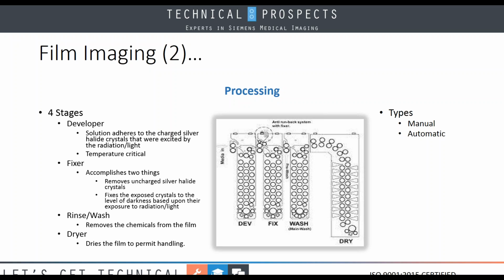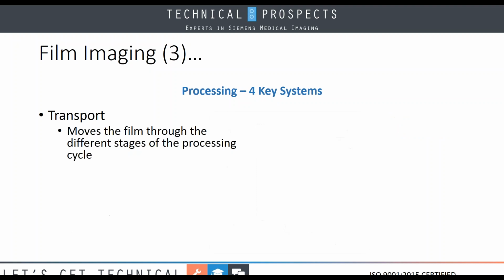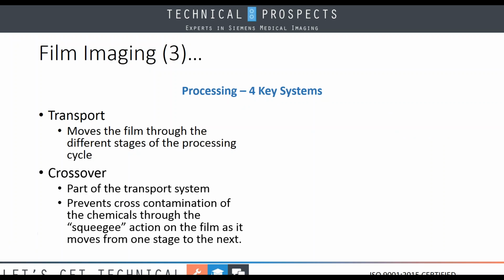And after a period of time in the wash, we then sent it over to the dryer, which then permitted us to safely handle the film without any type of damage. Now, looking at this, we found that there were four key systems involved in film processors. The biggest one was the transport, because this moved the film through the different stages of the processing cycle. The crossover, which was a part of the transport, all right, the biggest thing here is it used a squeegee action to prevent cross-contamination of the chemicals as it moved from one stage into the other. This could compromise the chemicals, and that would make a great deal of work for the appropriate field engineer out there in the field.